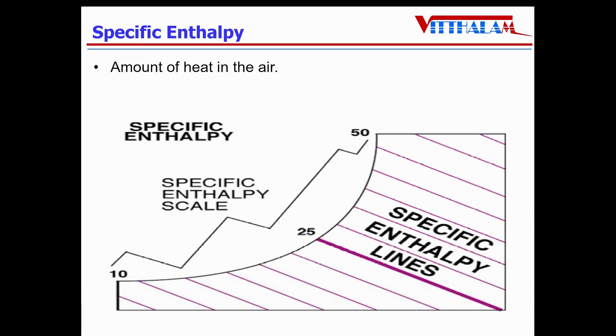Specific enthalpy, which is nothing but amount of heat in the air. As the name indicates, specific means per kg. So the unit will be either kilojoule per kg of dry air or kilocalorie per kg of dry air. It is also straight inclined lines, uniformly spaced like wet bulb temperature.